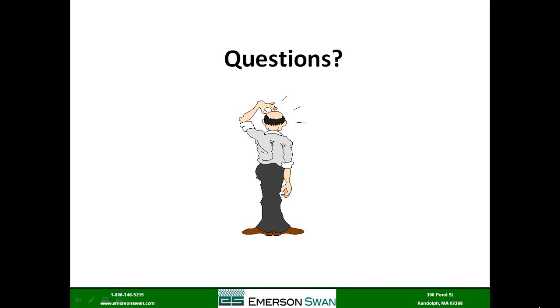Right. Again, moderation is the key here. Again, no more than 3 to 5 degrees, no less than 6 to 8 hours. Then I think it makes some sense. And again, if you're going away on vacation for 2 weeks, well, duh, that's a gimme. So setback's one of those interesting things. It's a great concept. It gets applied kind of poorly.